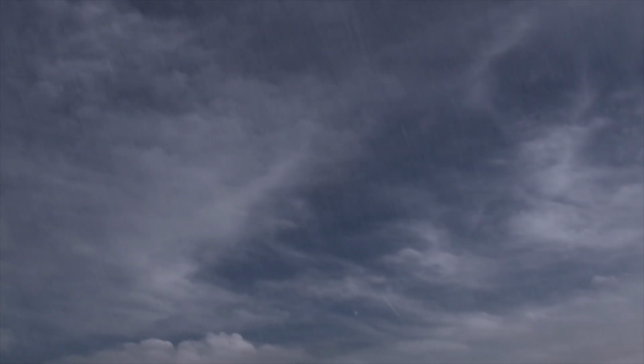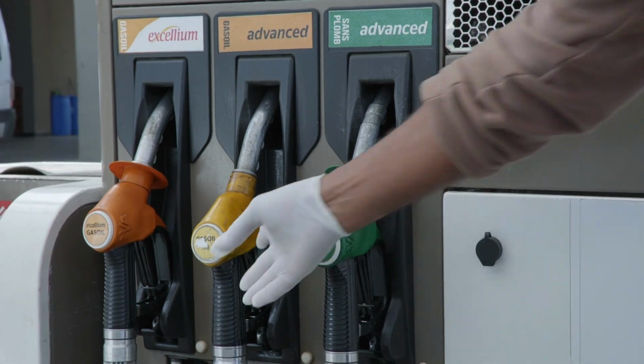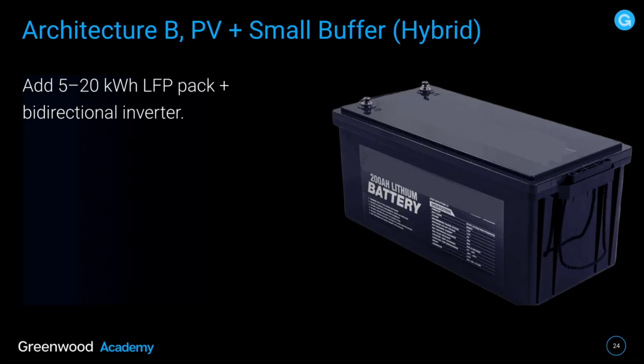Cons: no guarantee under clouds, pull down. Diesel remains the primary source. So that's the thing. Without that battery storage component, you are relying on the sun to reduce those loads. So we're going to add 5 to 20 kilowatt hours of battery and a bidirectional inverter in this situation.